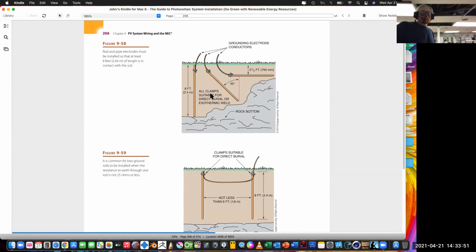So you start to see some weird things where they try to cut corners, where they can't go 8 feet because there's rocks down here, and then you've got to go to the right. Well, rock doesn't really hold water. Rock is not a good ground material. Ground material needs to be dirt, dirt with water and moisture in it. Sand is not dirt. It can be moist, but it is not good ground. Moisture is what attracts the electrons down into the earth.